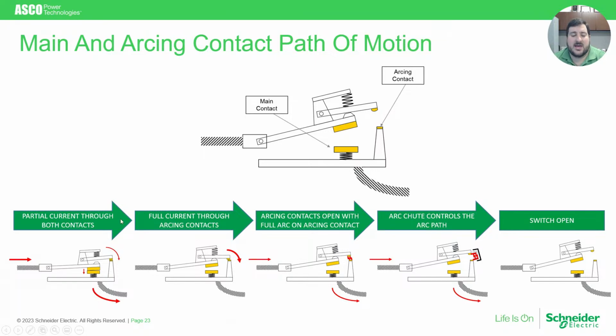What does that look like? How does that happen? Well, below here, you can actually see a very broken down sequence of what it looks like as the contacts are opening in the switch. So below, you can see that normally when that contact is closed and you're connected to that source, both the main contact and the arcing contacts are in a closed position. Current is flowing through both sets of contacts. However, due to electrical laws, the majority of the current is, of course, flowing through the main contact at that point in time. And it will stay in this state for an indefinite period of time until it requires to open that contact, say during a transfer to the other source. When you're opening the contact, the main contact will disconnect first.